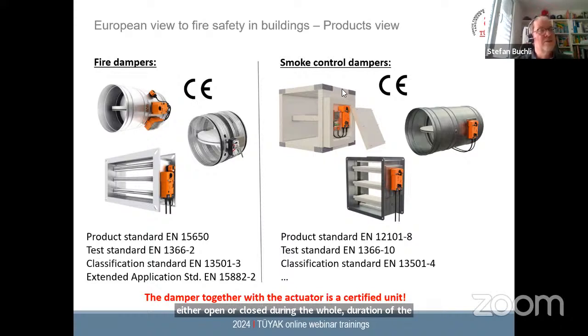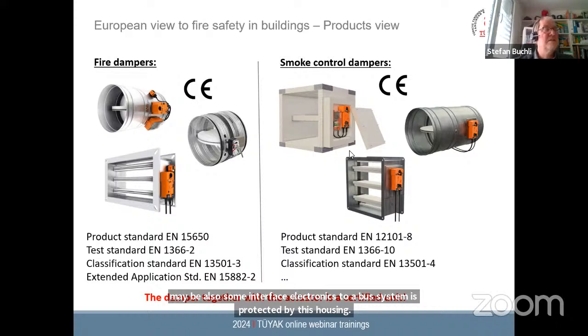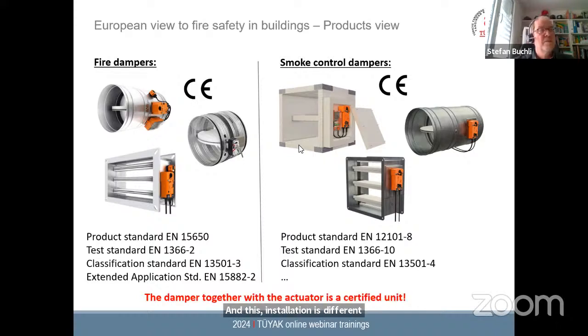And the one here on the left-hand side is fully protected. So this is really a solution where the damper is made not of steel but of calcium silicate. And you see the actuator, maybe also some interface electronics to a bus system, is protected by this housing. This installation is different from the first one, because it really can be operated by the fire brigade for typically half an hour, but then the temperature follows the standard time temperature curve. So you can have almost 1000 degrees C outside of the damper and still operate it for this half an hour. So it's a little bit of a different requirement than in the US.